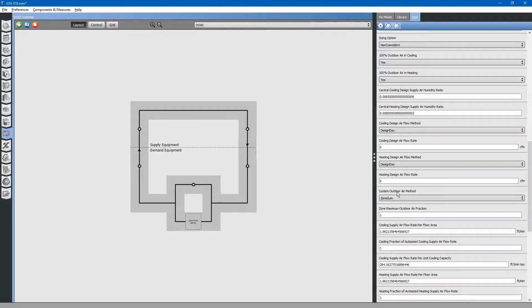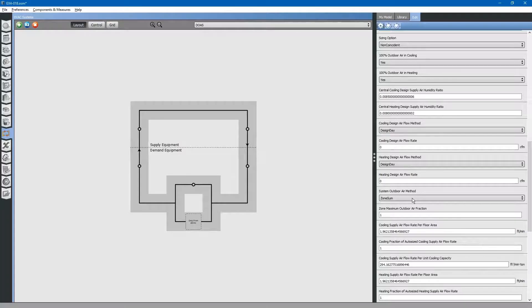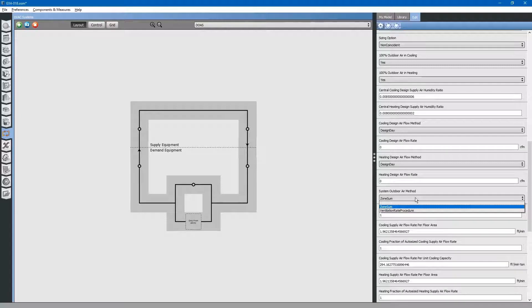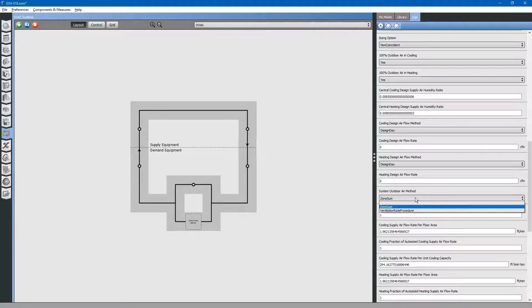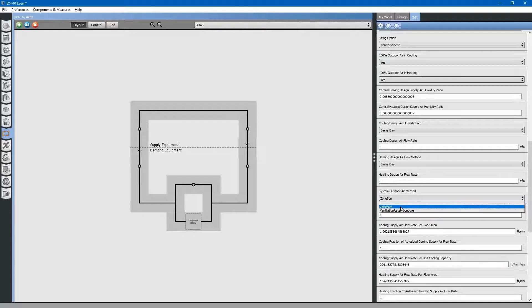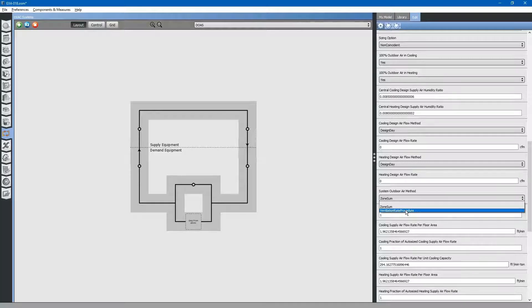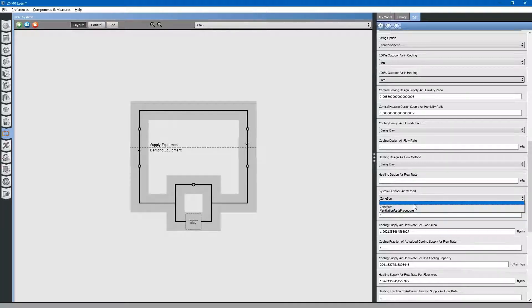Then, system outdoor air method. We only have constant volume diffusers in the system. There will be no modulation of the air flow in the system. We will just go with zone sum. If you do have modulation in the system with VAV boxes, you might go with the ventilation rate procedure.